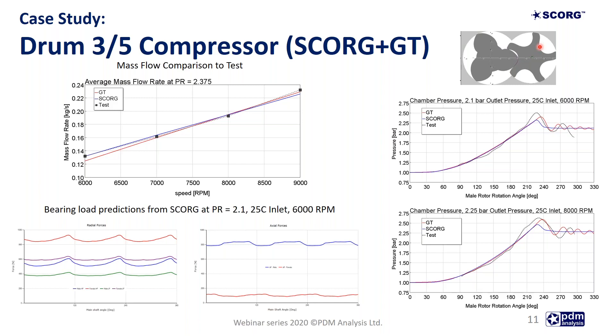The results obtained by SCORG thermodynamics and GT Suite were compared with experimental data. It can be observed that the alignment of both models with experiment is very good. Additionally, the GT model, which uses 1D flow calculation for ports, provides an idea of the oscillations at the discharge of the compressor. Bearing forces are calculated based on the performance predictions from either SCORG or GT Suite and are used for selection of bearings.